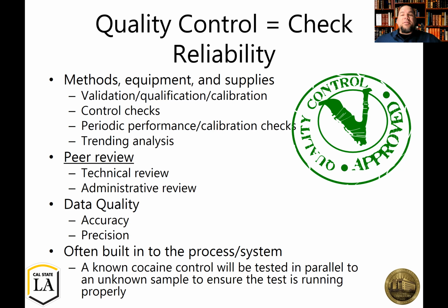If you start to see a dip in the sensitivity of the instrument to a particular assay, then a good QA/QC program is going to start detecting that. That's important, of course, because say your detector starts to stop working, you could artificially be getting less results, and it's really due to the instrumentation.